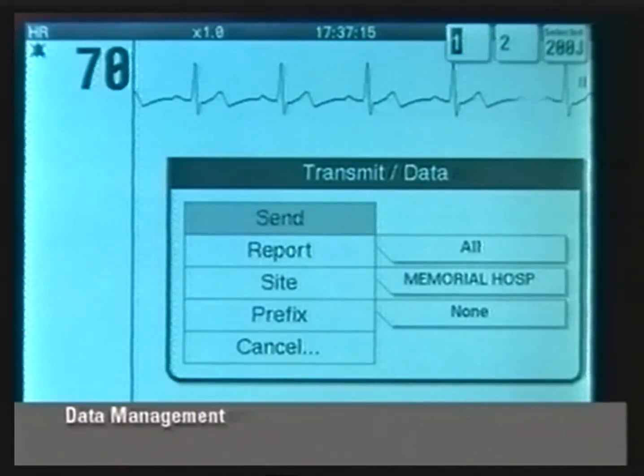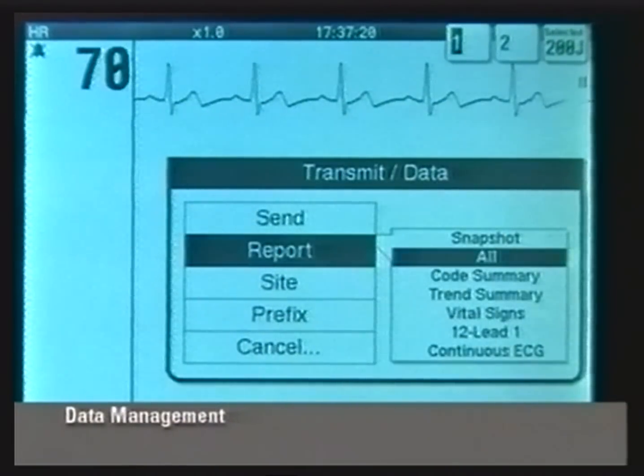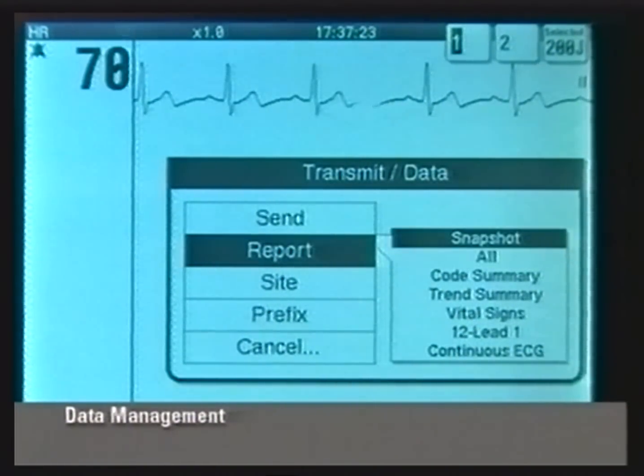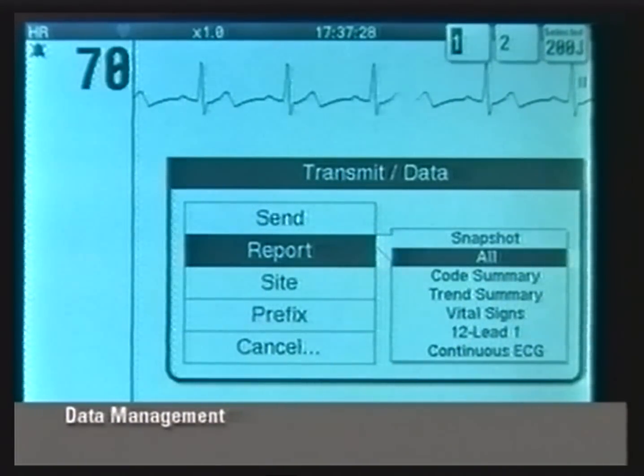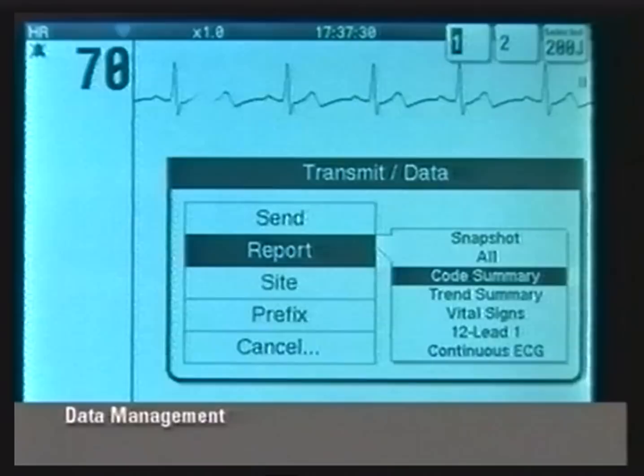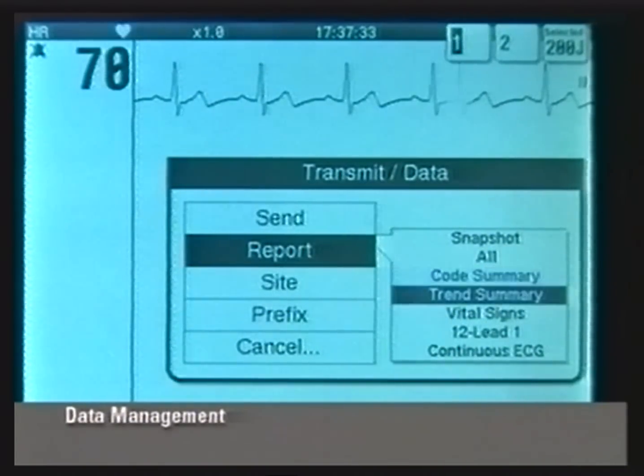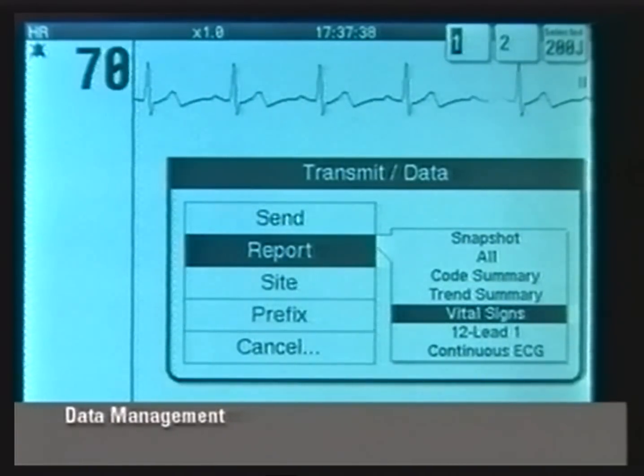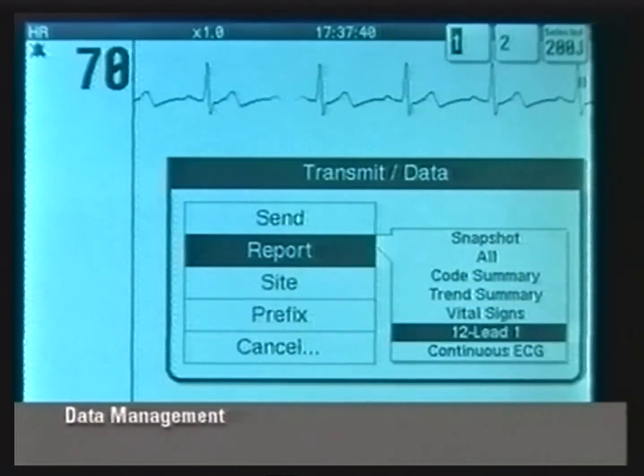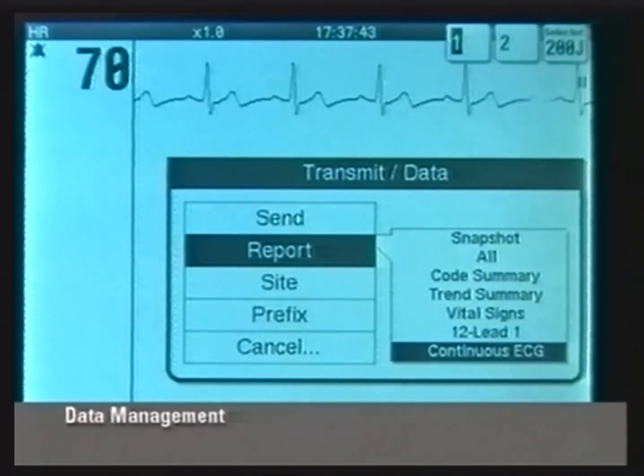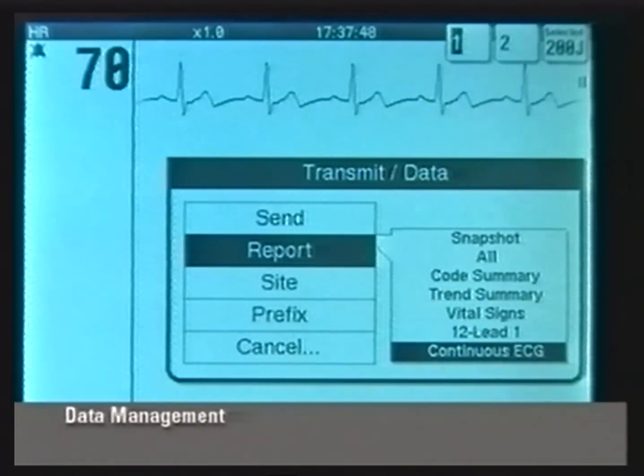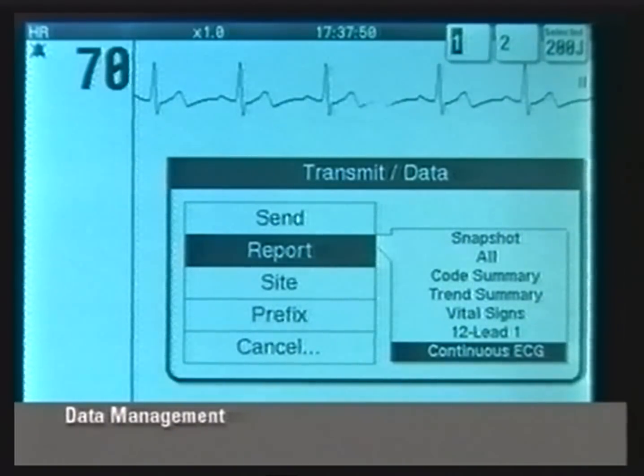If any of these settings are incorrect, select the setting to be changed. Select Report to display the report list. Choose the desired report. Snapshot sends the snapshot report. All sends all reports on the list. Code Summary sends the critical event report. Trend Summary sends the trend summary report. Vital Signs sends the vital signs report. 12 Lead sends the selected 12 lead report. Continuous ECG sends the continuous ECG report. A check mark indicates a report already sent successfully.